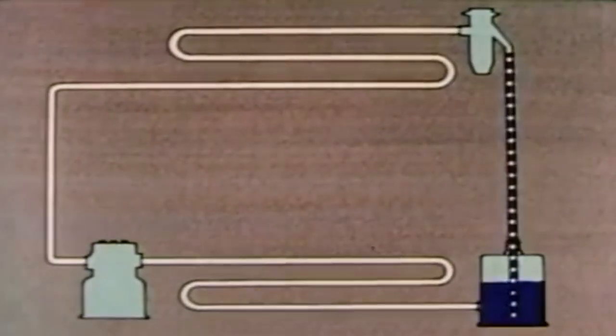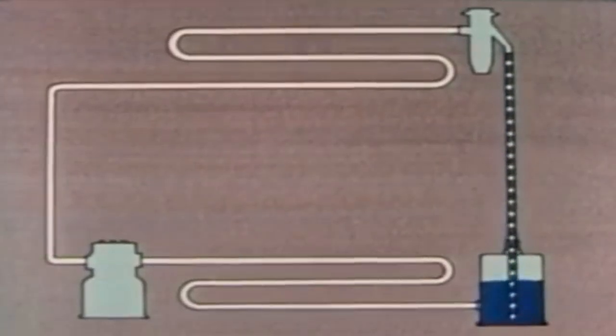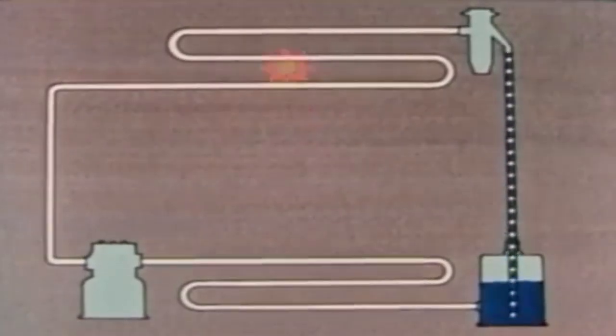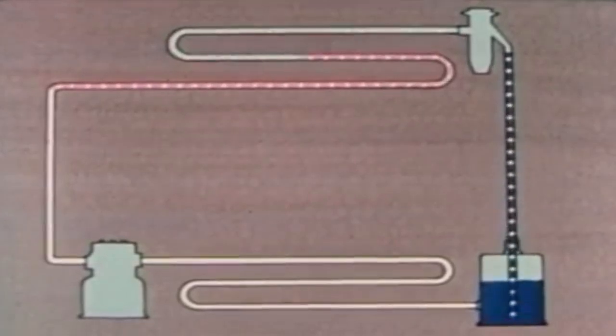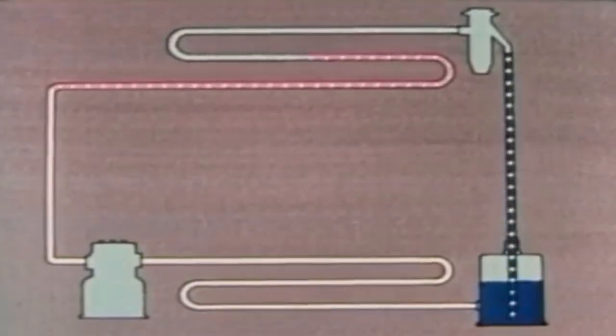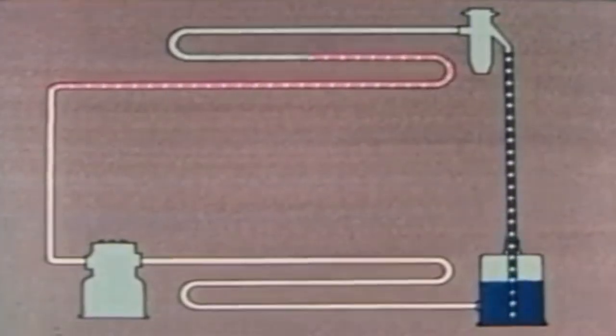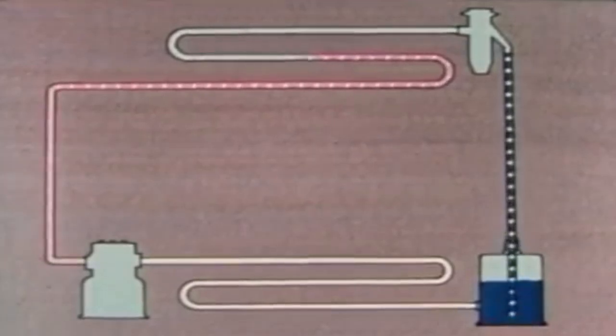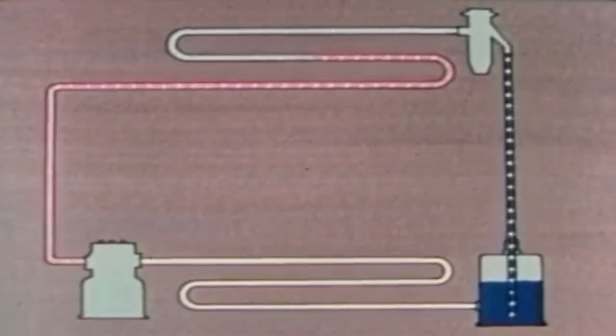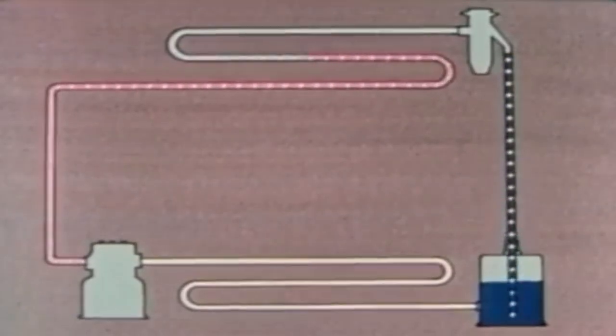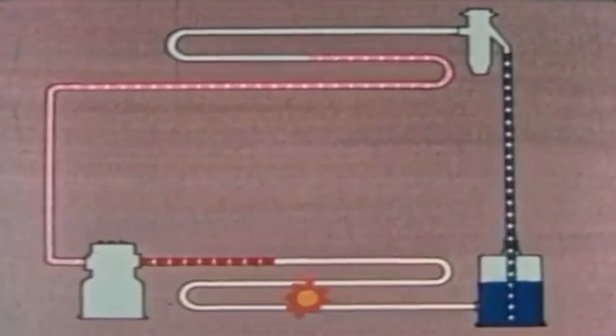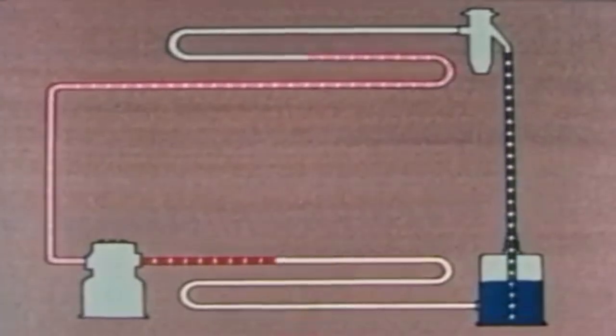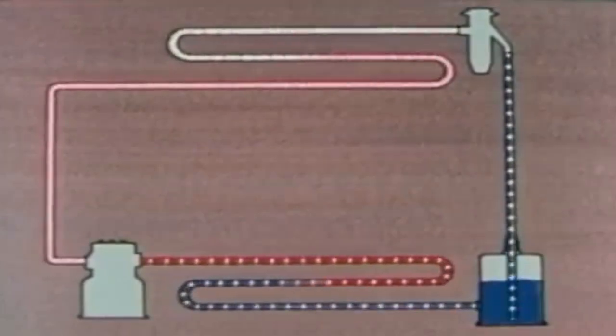Now let's review the whole thing. Refrigerant under high pressure flows from the receiver to the expansion valve. The valve causes a pressure drop. The evaporator takes in heat from the box — if anything in the box is hotter than the refrigerant, it gives up its heat to the refrigerant. As the refrigerant takes in heat, it changes from a liquid to a gas. The compressor sucks the vapor out of the evaporator and compresses it, increasing the pressure and temperature. The vapor is now hotter than the surrounding air, so in the condenser, heat is given off to the air. As the refrigerant loses its heat, it changes from a gas to a liquid and flows into the receiver.